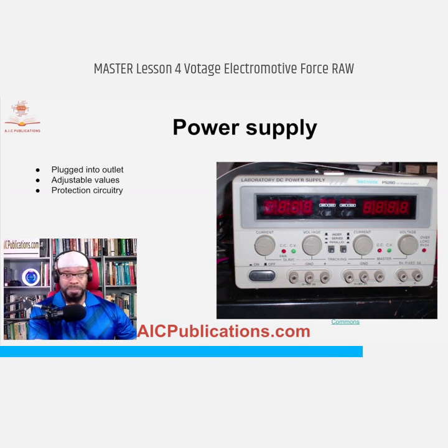That means if someone were to turn the supply on and connect the negative terminal into the positive terminal directly without a circuit in between, rather than destroying the power supply, it would simply shut it off and reset. In older power supplies where this feature was not included, engineers have to manually account for such an imbalance.